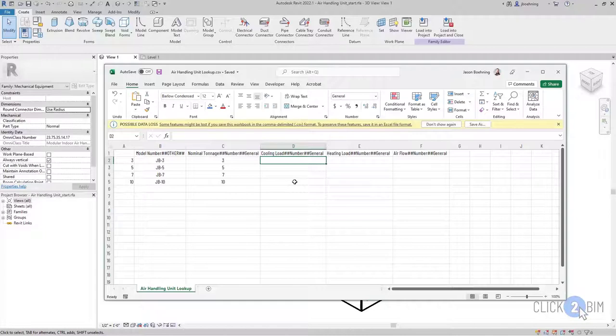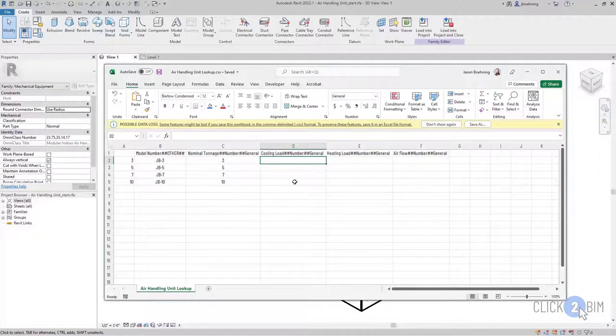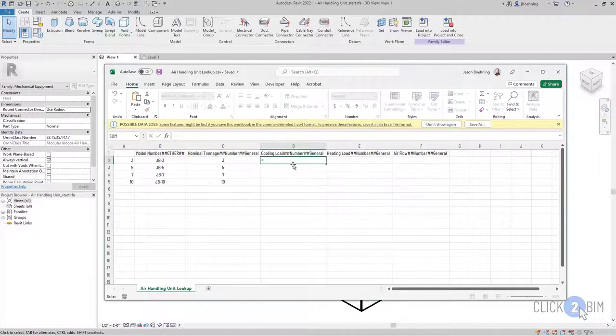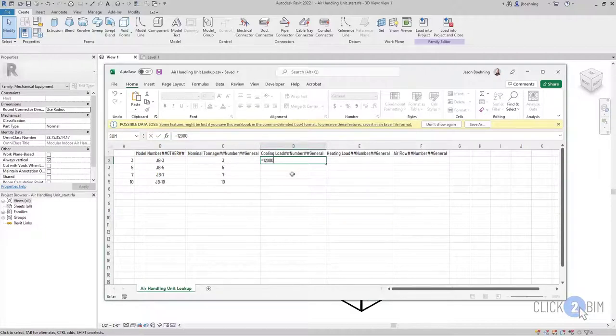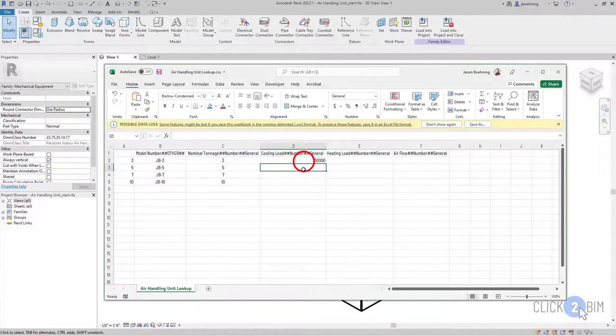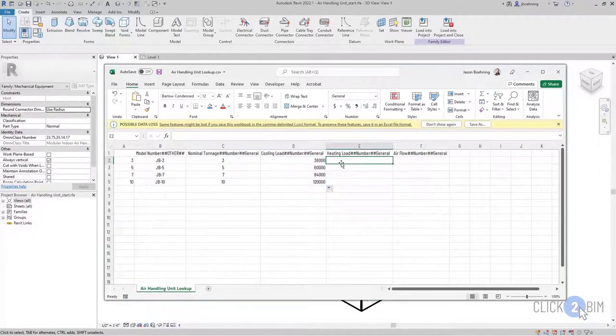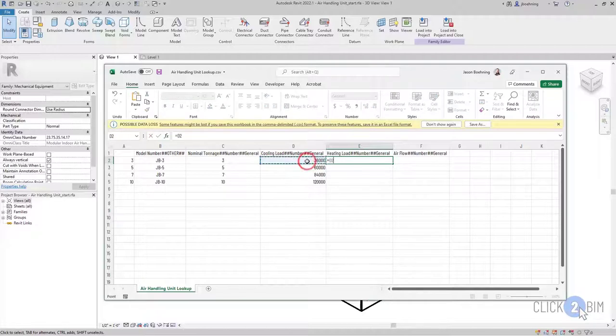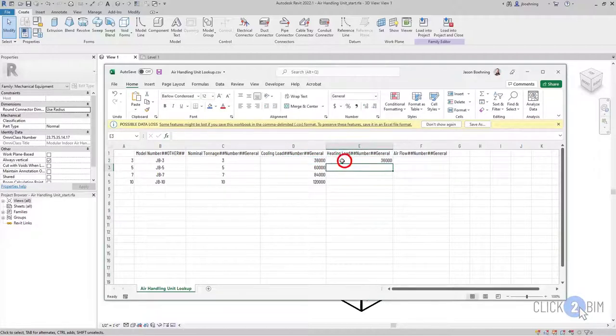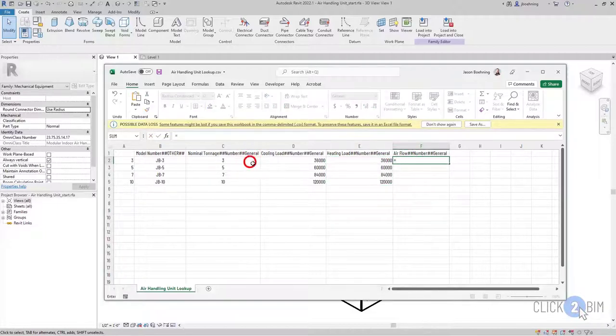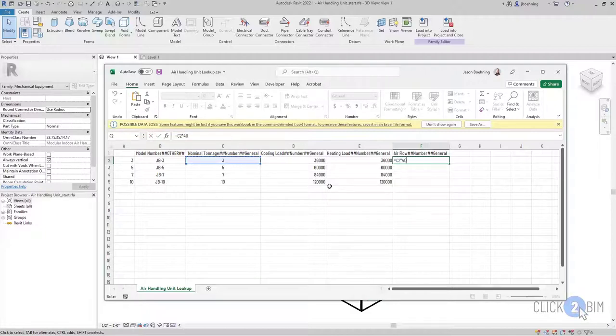So one of the benefits of using a CSV file is that you can use formulas in Excel, but just be aware that those formulas will not save with the CSV file. For example, let's say we want to define our cooling load based off of our nominal tonnage. So I'm going to enter an equal sign, and there are 12,000 BTU hours per ton, so 12,000, and then multiply that by our nominal tonnage. I'll enter another formula for the heating load to keep it simple, setting it equal to the cooling load. And then for the airflow, let's use another common rule of thumb, so our nominal tonnage multiplied by 400.